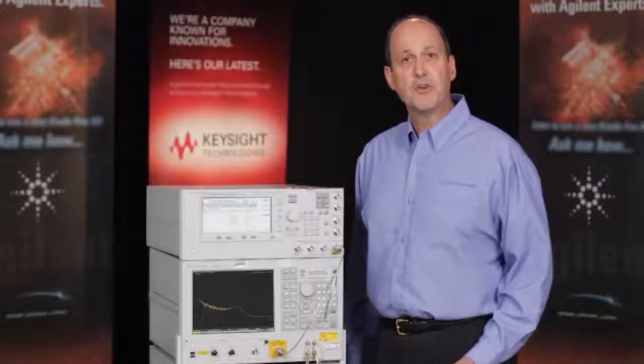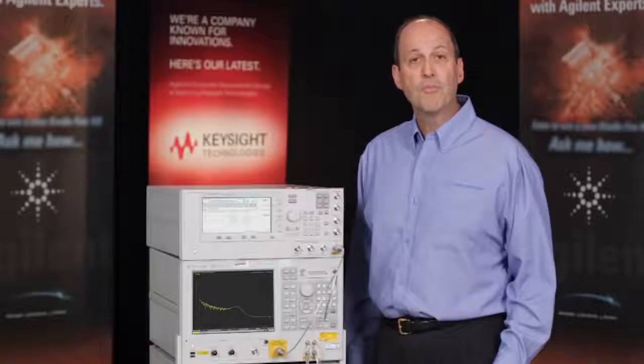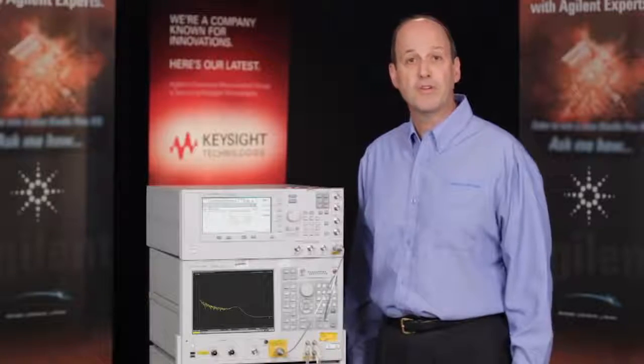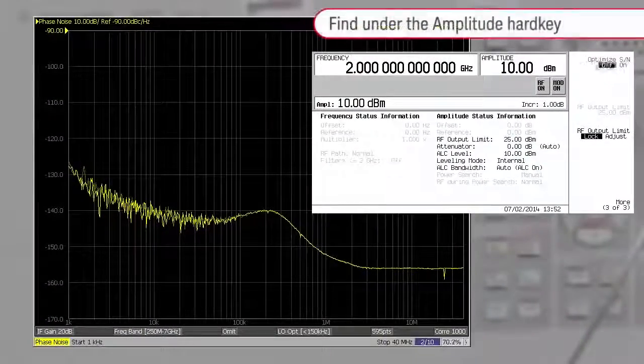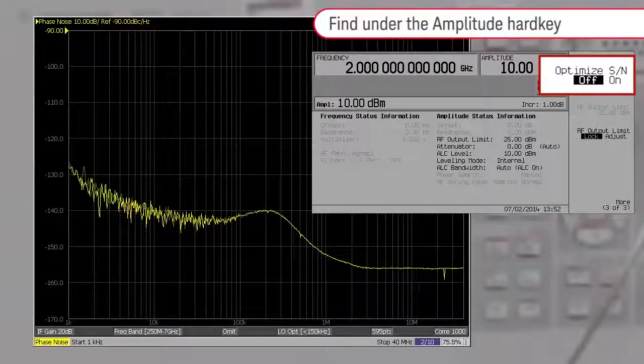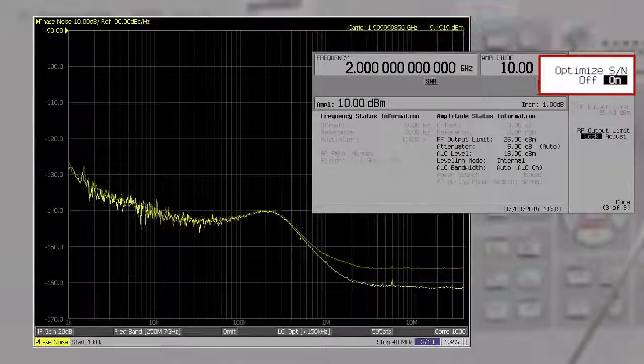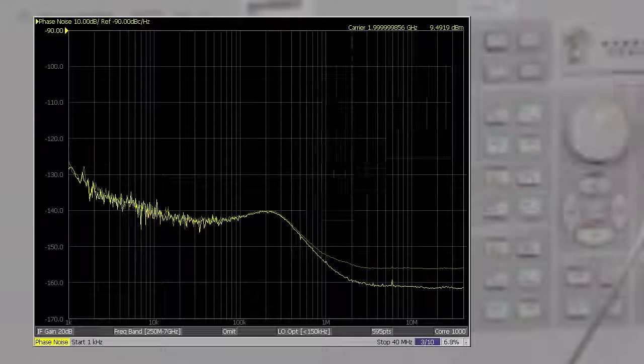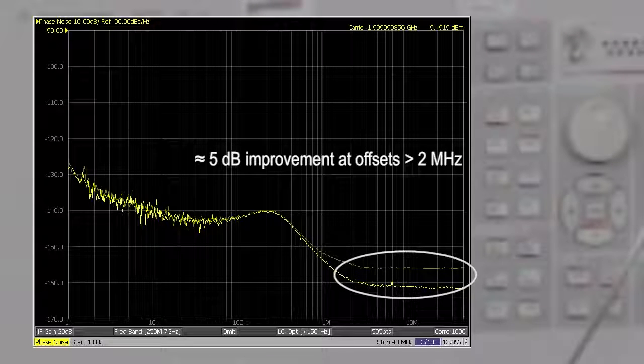We also have a signal to noise optimization mode that can improve broadband noise at greater than 1 megahertz offsets from carrier. You can find this under the amplitude key. By switching to optimize signal to noise, you can see about 5 dB improvement at offsets greater than 2 megahertz.